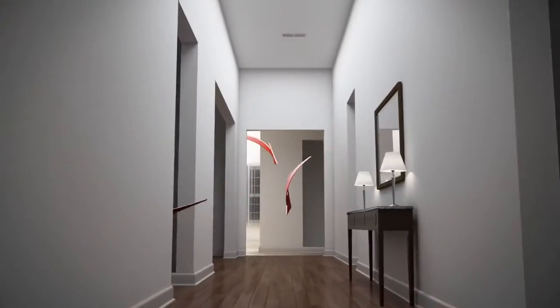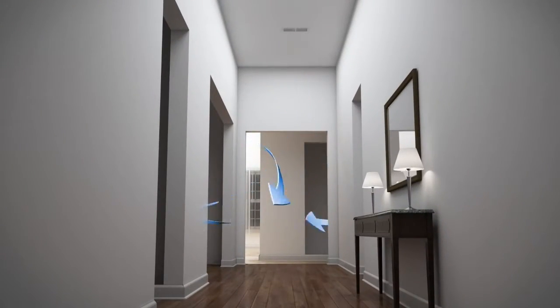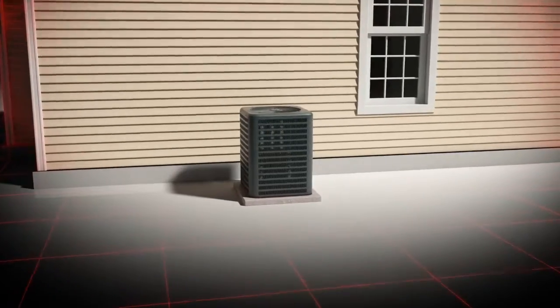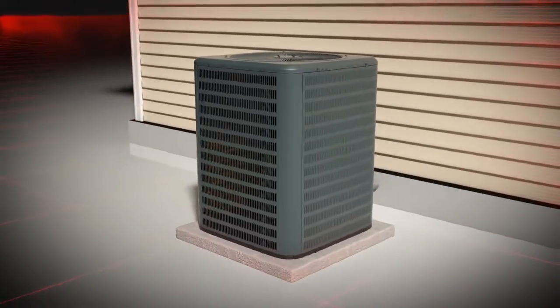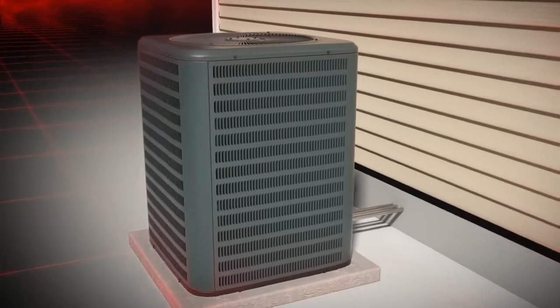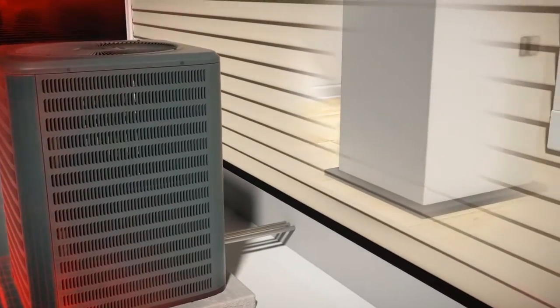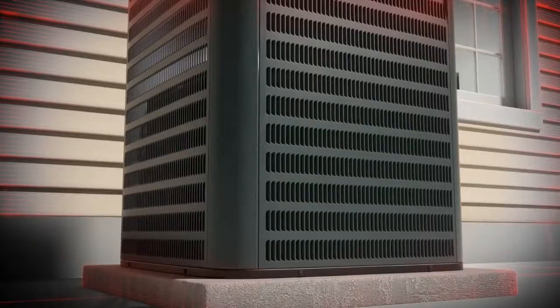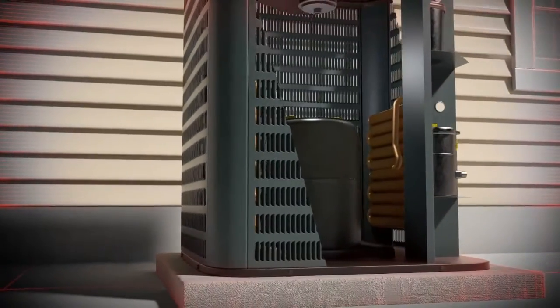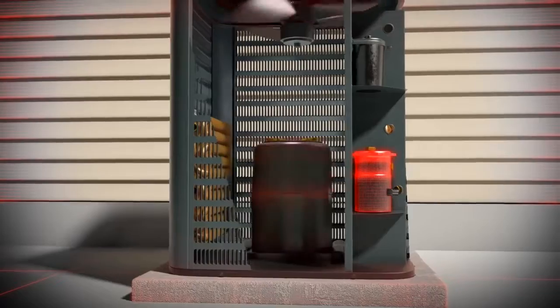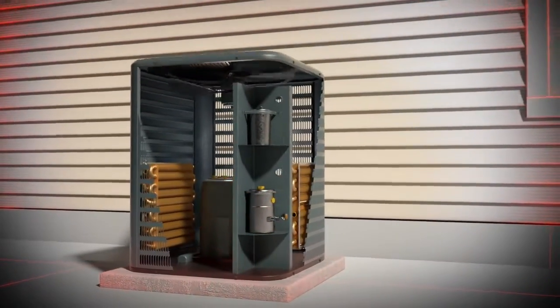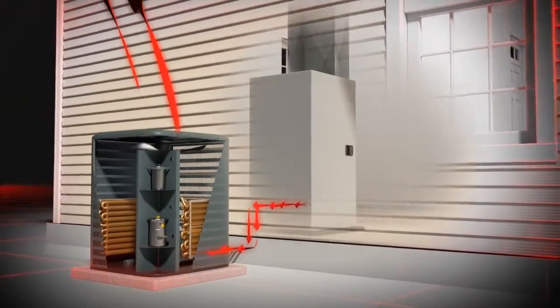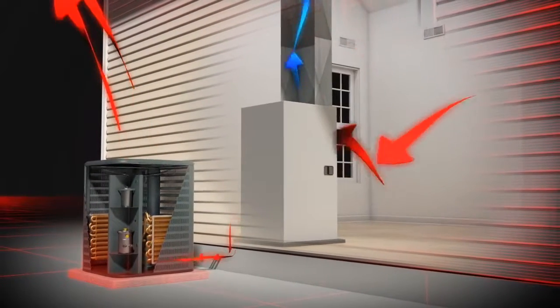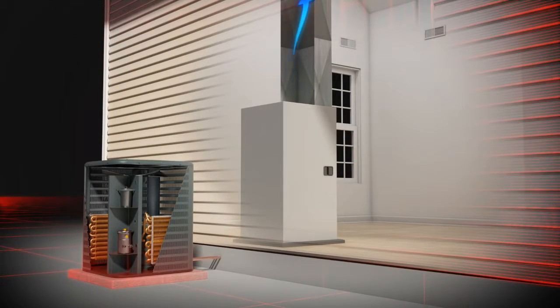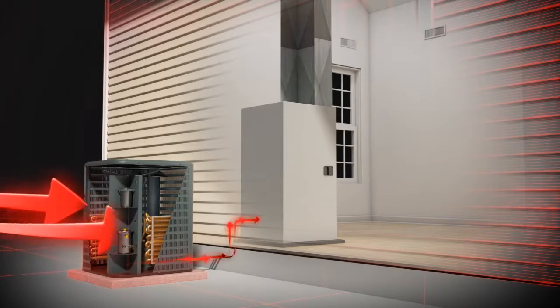Air source heat pumps utilize the ambient temperatures of the outside air as a heating source for residential heating. A refrigerant is pumped into an outdoor heat exchanger where the ambient air causes the refrigerant to boil. This refrigerant is then compressed to a superheated state before being pumped to an indoor plate heat exchanger, where it condenses and transfers heat to water, which will be used for space heating and hot water supply. The now liquid refrigerant is passed through an expansion valve where the pressure and temperature is reduced, before recirculating the refrigerant back into the outdoor heat exchanger, restarting the process.